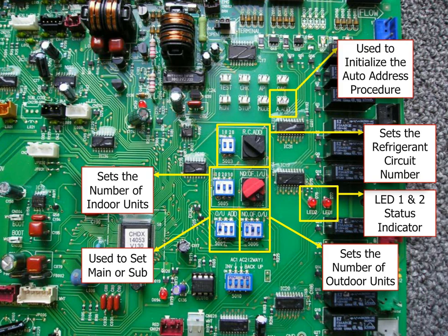The pins labeled A.ADD, CN100 are used to initiate the auto address procedure. When the auto address is in progress, the outdoor unit looks for all the indoor units connected to the SNet, and communicates with them. Once this procedure is completed, and correct, it is stored in the EEPROM chip.